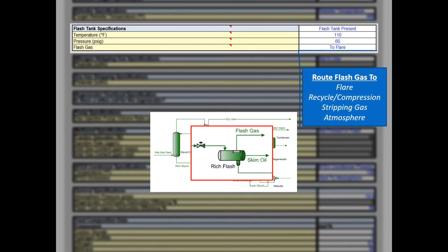The glycol absorber typically operates at relatively high pressures, which helps the glycol absorb more water. The regeneration step, however, operates close to atmospheric pressure. As the rich glycol is reduced in pressure, absorbed hydrocarbons will vaporize in the rich flash tank. Users will define whether a rich flash tank is present using the drop-down for flash tank specifications. For sites with flash tanks, define the operating temperature, pressure, and where the flash vapors are routed. There are four options: vapors can be sent to a flare, compressed and recycled back to the glycol contactor, used as stripping gas in the regenerator, or vented to the atmosphere.